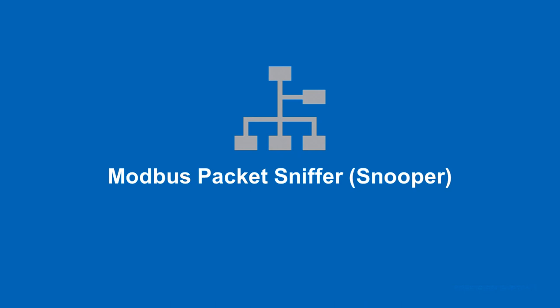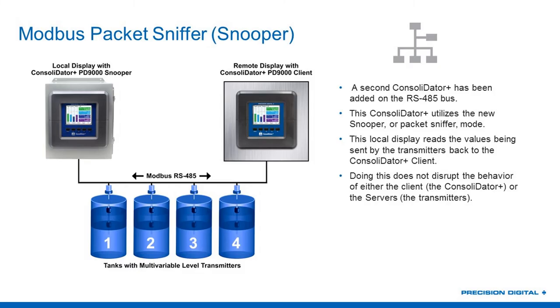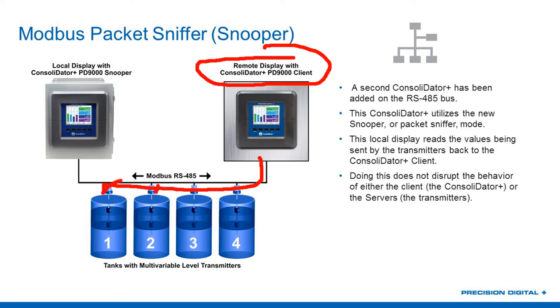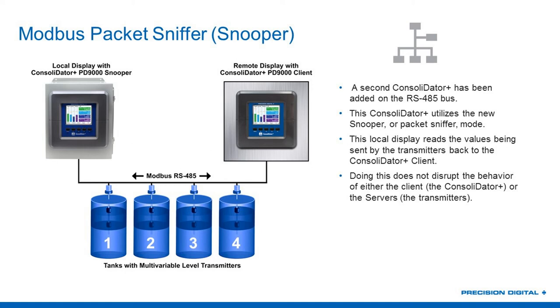The second feature is the Modbus Packet Sniffer or Snooper Mode. What that lets you do is read information on the Modbus communication bus without the need to reprogram anything that is already active in your system. We're going to take a look at an example where we assume the system we just looked at is active — I have my Modbus client in the control room reading out information from four multivariable level tanks, but I'd really like to have a display pole-mounted right next to those tanks out in the field.